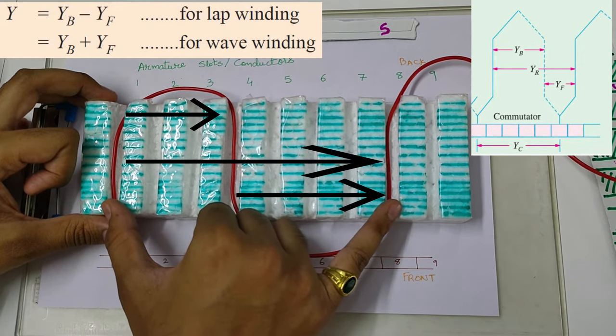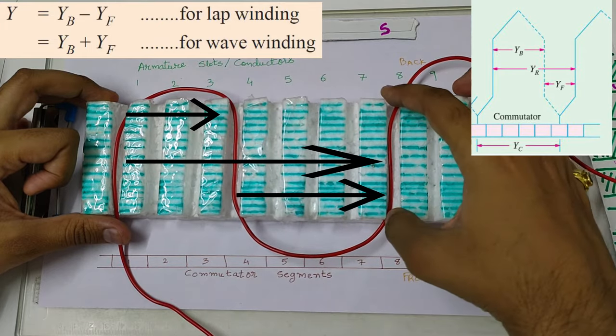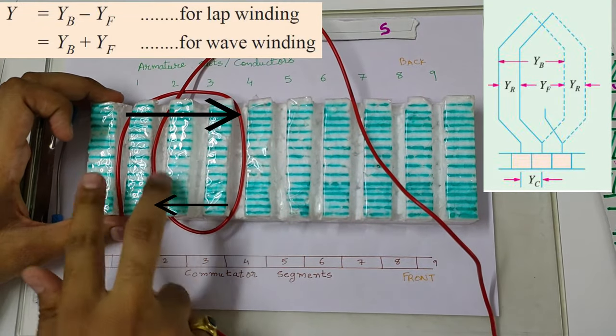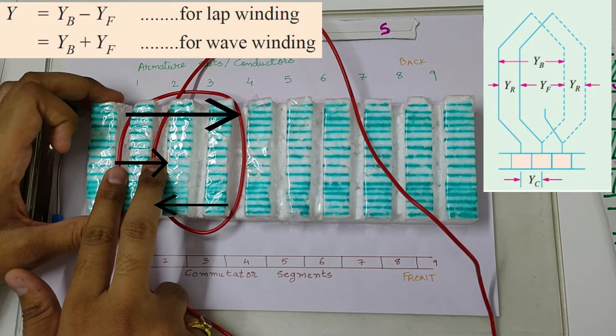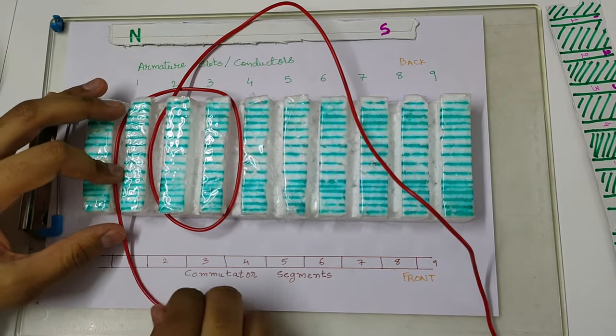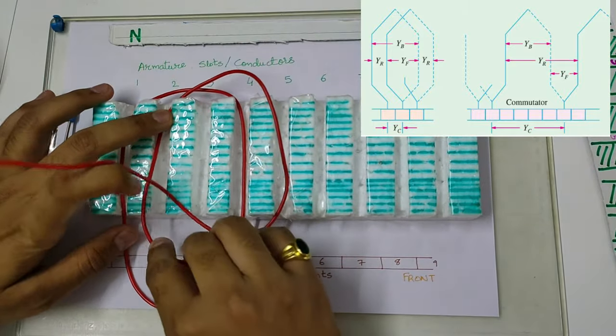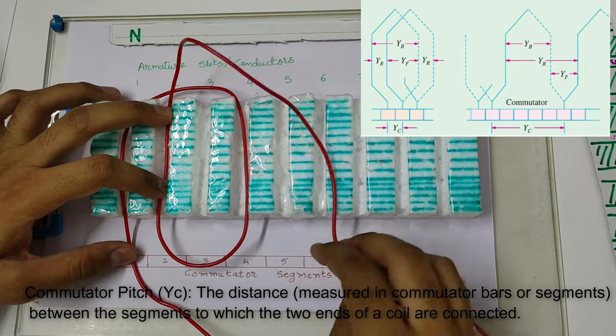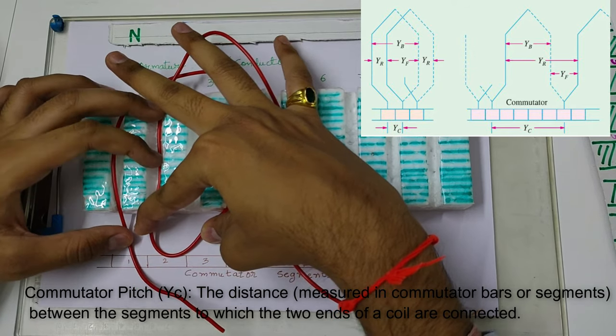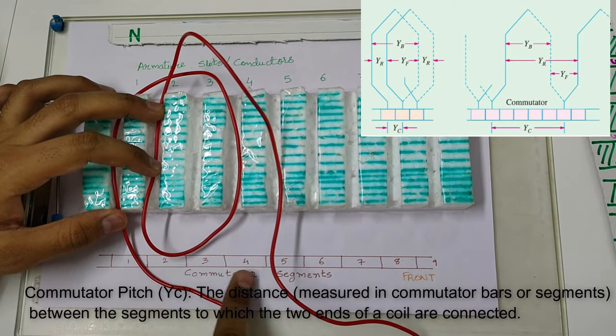In case of a wave winding, the resultant pitch or winding pitch is equal to back pitch plus front pitch — it adds up because the next winding starts further along. In case of a lap winding, it would be back pitch minus front pitch that gives us the resultant distance. For lap winding, it is YB minus YF. Now, what is commutator pitch? All these windings will always be connected to each commutator segment. If the first turn is connected with commutator segment 1 and the second turn is connected with commutator segment 2, then the commutator pitch is 2 minus 1, that is 1. Commutator pitch is always calculated in terms of number of commutator segments.